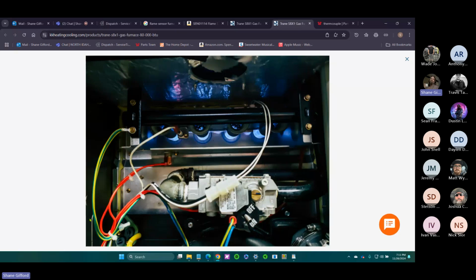So once it goes through all your safeties, your rollouts, your high limits, stuff like that, your flame, from here it's all timed. Most of the stuff that we see is not going to have any sort of timing sequence, but just in case we run into this, it's going to pull induction, close the pressure switch, and then everything is timed and it's going to count. And then your glow stick, your igniter, is going to start to go. Most of the time, those need about 8 to 12 seconds to get to ignition temperature, meaning that by the time the gas valve opens and starts dumping gas in here, that hot surface igniter is going to be hot enough to immediately combust that gas, and then you're running, you're good.